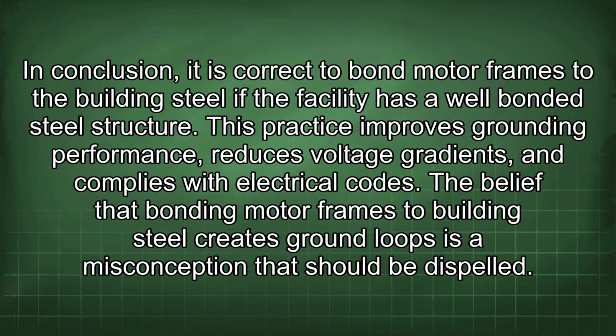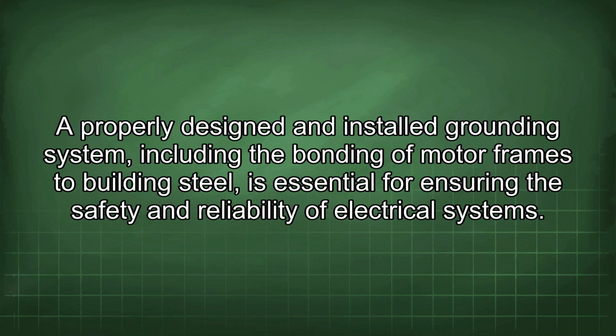In conclusion, it is correct to bond motor frames to the building steel if the facility has a well-bonded steel structure. This practice improves grounding performance, reduces voltage gradients, and complies with electrical codes. The belief that bonding motor frames to building steel creates ground loops is a misconception that should be dispelled. A properly designed and installed grounding system, including the bonding of motor frames to building steel, is essential for ensuring the safety and reliability of electrical systems.